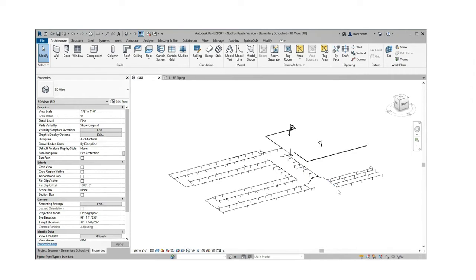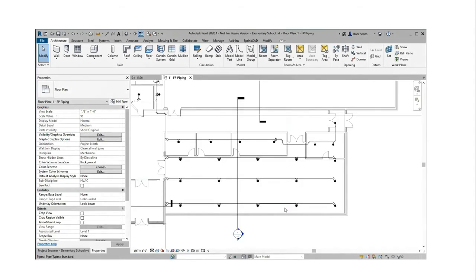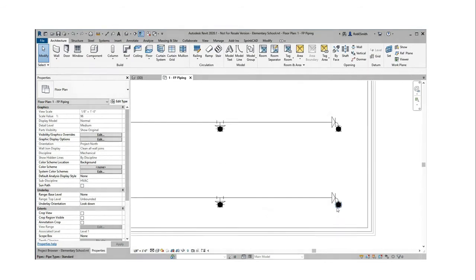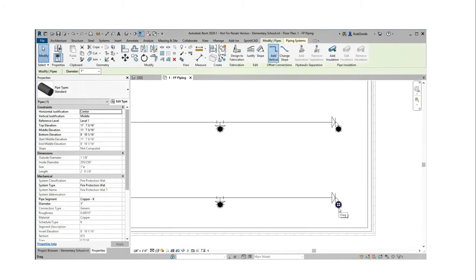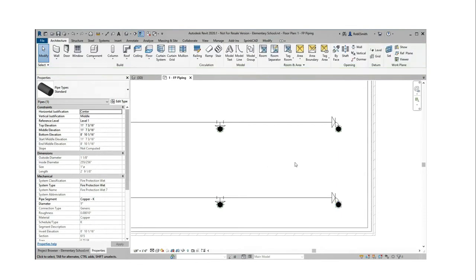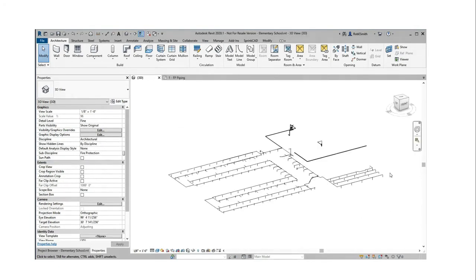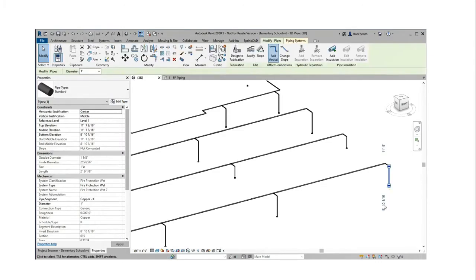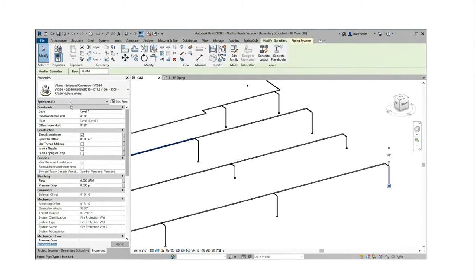You'd probably perform at least two calculations on a floor like this because you've also got a loop/grid section to calculate. Looking at the pipe properties: the drop nipple is one inch, the branch line is inch and a quarter copper. This whole system was designed in copper — which means whoever got the contract is floating in cash. In a 3D view you can confirm: copper, one-inch drops. Now taking a look at the sprinkler head — that is a Viking head.